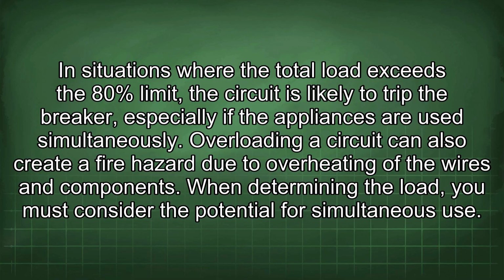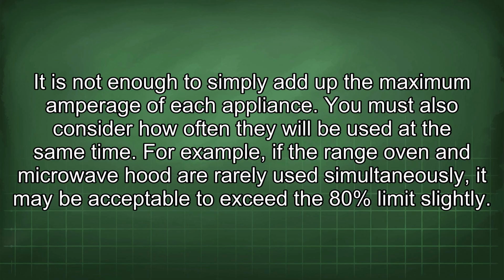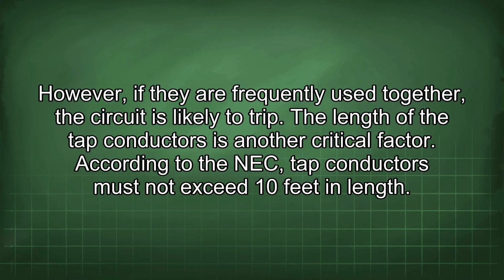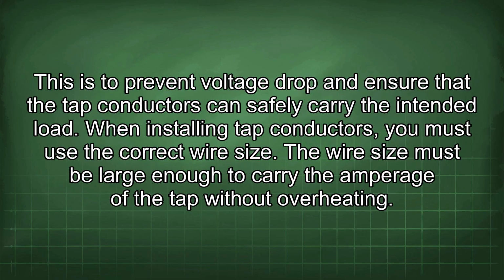When determining the load, you must consider the potential for simultaneous use. It is not enough to simply add up the maximum amperage of each appliance. You must also consider how often they will be used at the same time. For example, if the range oven and microwave hood are rarely used simultaneously, it may be acceptable to exceed the 80% limit slightly. However, if they are frequently used together, the circuit is likely to trip. The length of the tap conductors is another critical factor. According to the NEC, tap conductors must not exceed 10 feet in length. This is to prevent voltage drop and ensure that the tap conductors can safely carry the intended load.